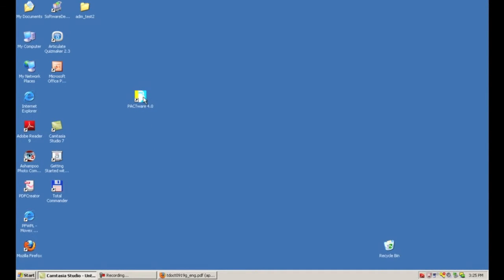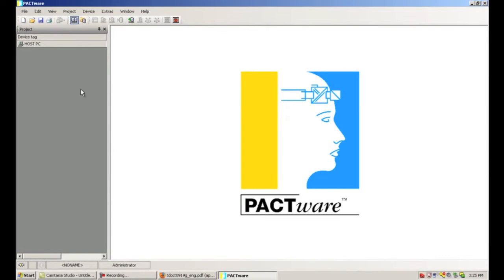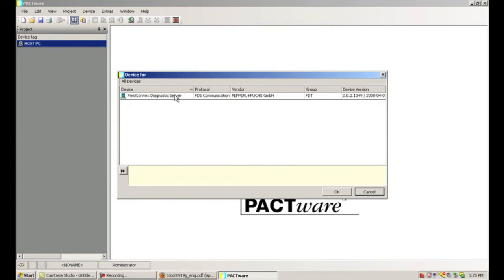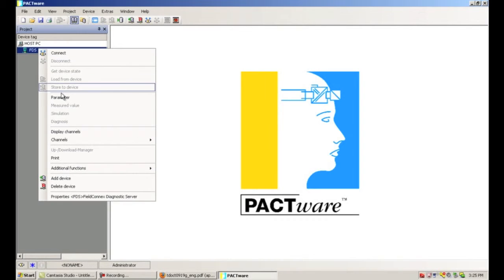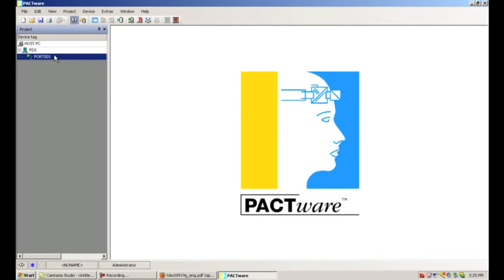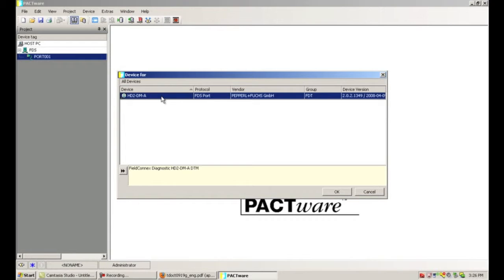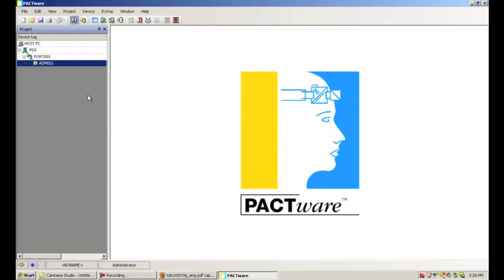The next step is to open up Pactware — Pactware 4.0 should have an icon on your desktop. The first step is to build our project in the project window. If we right-click on the host PC, we can add a device, and the first device we're going to add is the FieldConnex Diagnostic Server — this is server software running in the background on your PC. Then we right-click on the FDS, add another device, and this time we add the FDS port. Next, we right-click on the port, add another device, and select the HD2DMA — the Stationary Diagnostic Module — and click OK. This builds up our project to connect to one ADM.